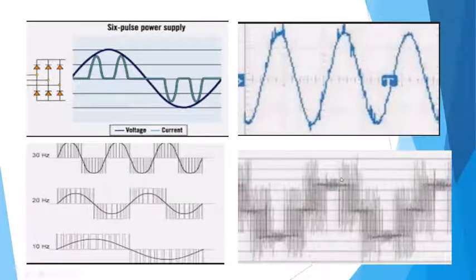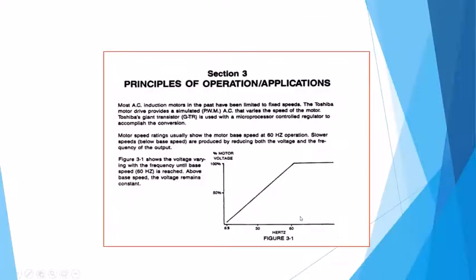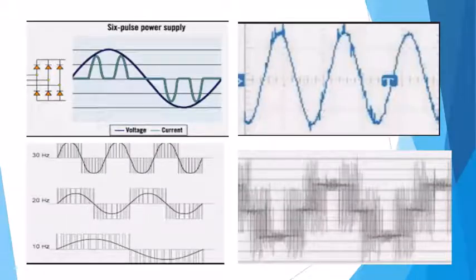So you put this on, and after a year or two, all of a sudden you had a motor failure, depending on the motor lengths. And then depending on what the ripple voltages and things are, all of a sudden you get a lot of effect. Again, don't get me wrong, VFDs do have their place. You can easily control that pump to make it function and operate. But just be aware that you've got to be watching that output peak voltage, and you've got to watch the noise disturbances out on the front power line, because the power company has what they call IEEE 519, which they want to keep you within tolerance so that this noise and frequency doesn't go feeding back to other customers.